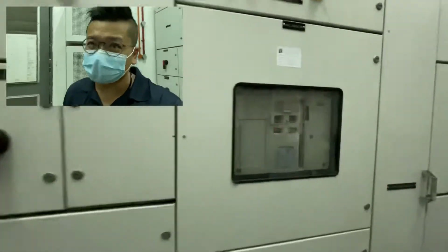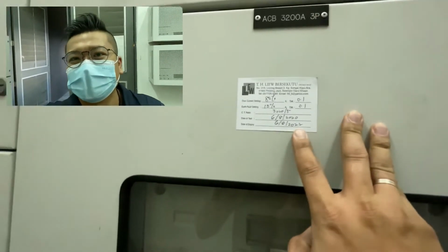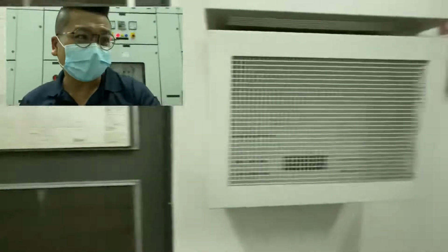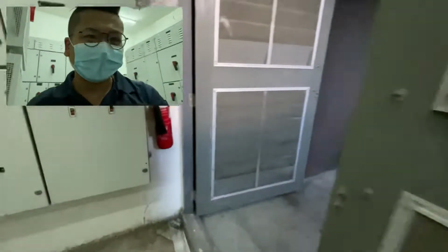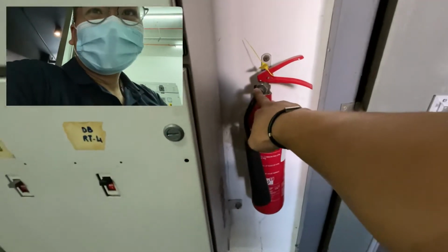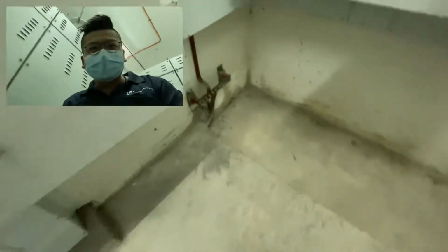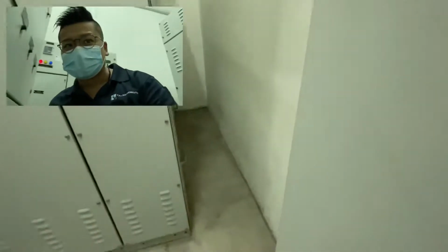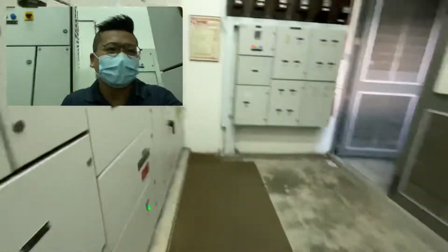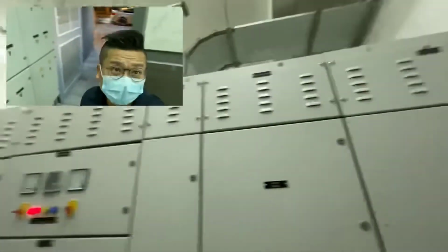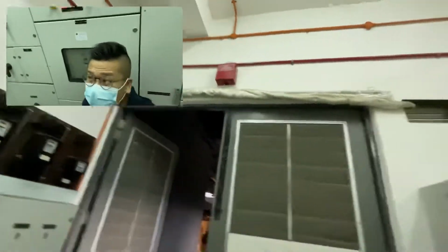So first of all, we need to double check calibration date and make sure single line drawing is available. Fire extinguisher is hang located beside the entrance. Rubber mat is in place. Earthing connection is correct. All panel is properly closed. No obstruction on the walkway. Clean, dry, no moisture, no leaking from above. The door fire curtain is in place.